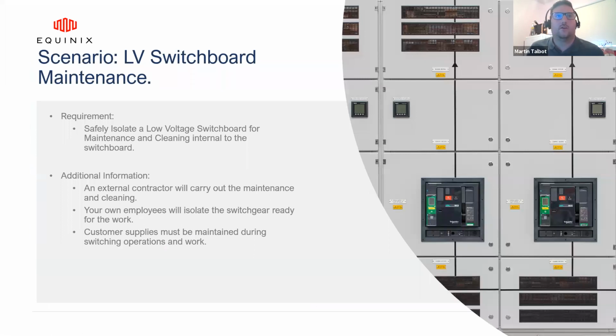Okay, so what we're going to look at as our scenario is that we are going to safely isolate a low voltage switchboard for maintenance and cleaning internal to the switchboard. An external contractor will carry out the maintenance. Your own employees will isolate the switchgear ready for the work, and the customer supplies must be maintained during switching operations and work. Because we're a data center, a major part of our business is supplying customers with power. We want to do that continuously and safely.